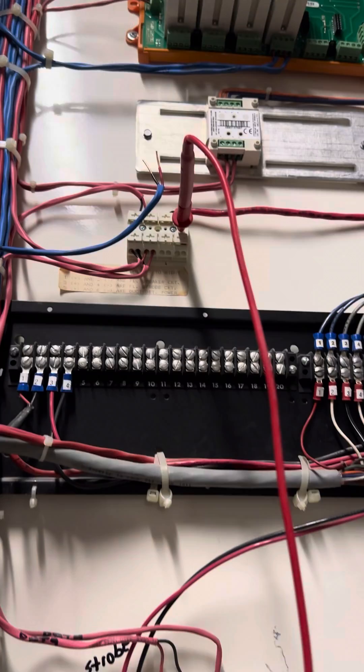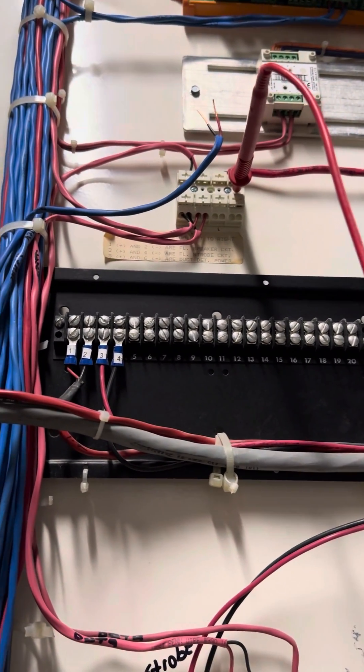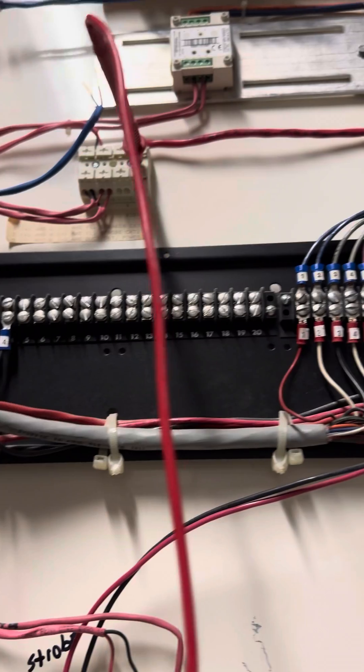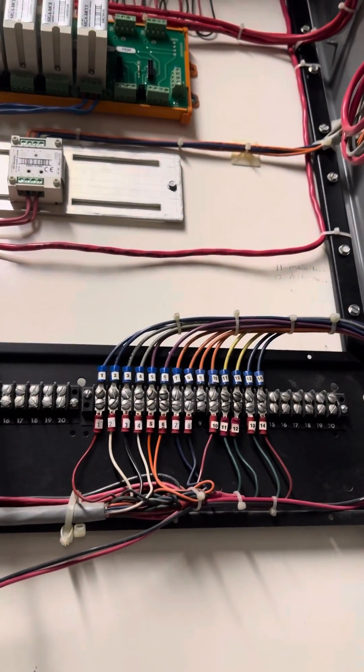What I typically do is find the speaker circuit, which we have in this termination box. I disconnected it, so that blue tab is the speaker feed which has 24 volts coming from the amp, and then that is our output right up there in front of my finger goes out to the field.